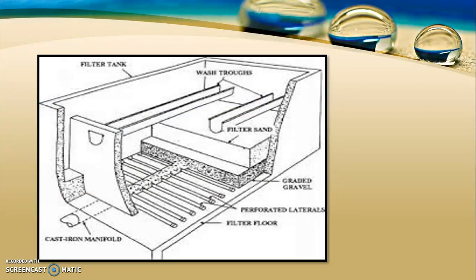This shows the structure of a rapid sand filter. It has a gravel layer, a sand layer, and a wash water trough above the sand layer. At the bottom is an under-draining system from where the filtered water is passed. Water first enters the filter sand, then the gravel, and then passes through perforated laterals to a central manifold, and from there to further processes.